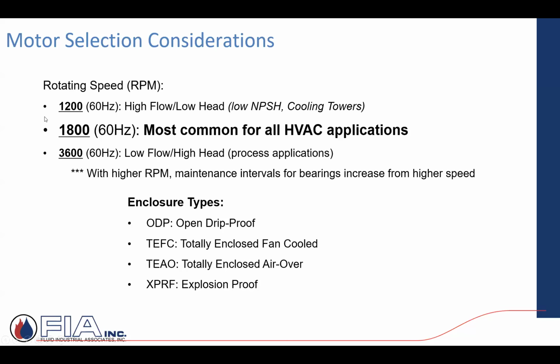And again, motor speeds. 1200: high flow, low head. So a lot of flow rate, gallons per minute, very low pressure drop, maybe low NPSH, or more commonly, it might be a cooling tower. Might be an application you're going to bump up against. 1800 is absolutely the most common that we're going to see in a closed loop heating and cooling application. And then 3600 RPM: very low flow, but very high head. Process is a very common application, perhaps.